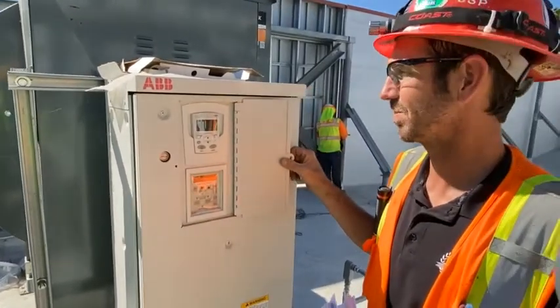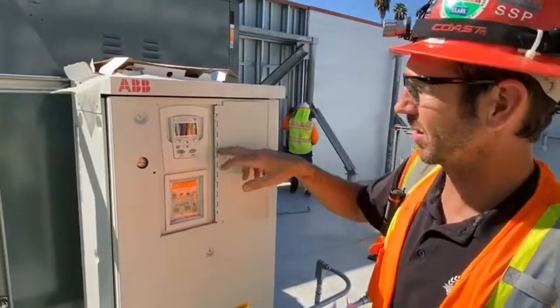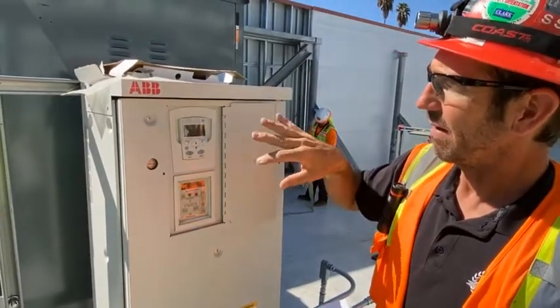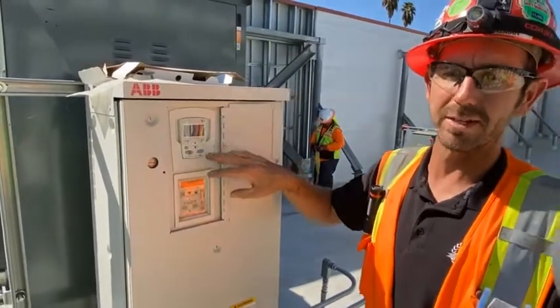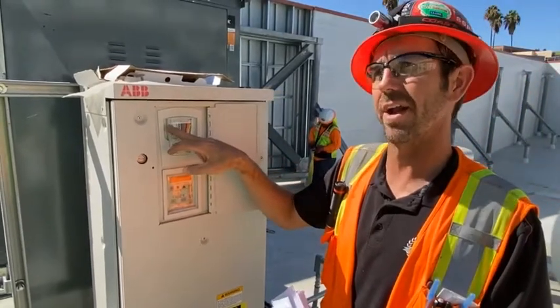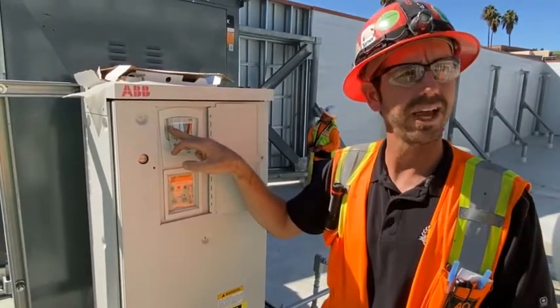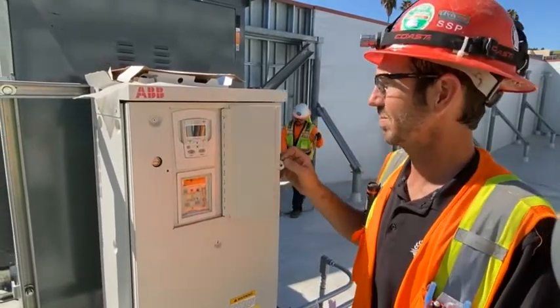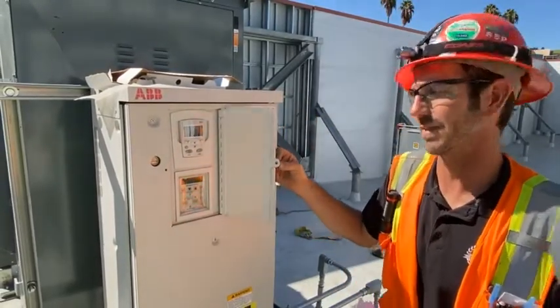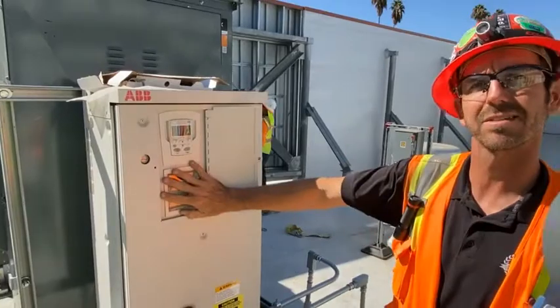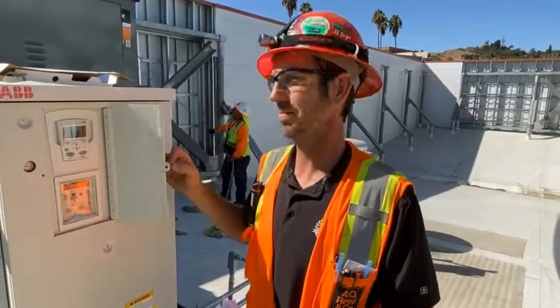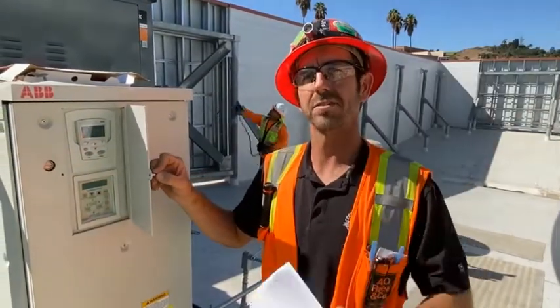It is a belt-driven unit, but we'll go over that tomorrow. For this fan, the most important thing is that we remain in auto. If we're not in auto, it can't turn on that hood downstairs, okay? That's all I've got on this VFD. Again, we're not using the bypass. Okay? We'll make it over to the other roof.